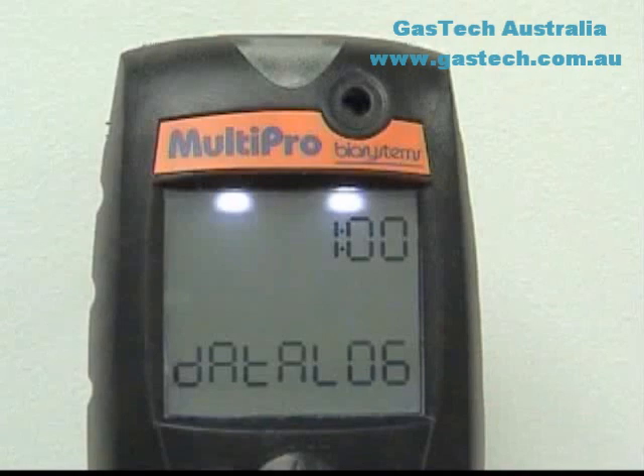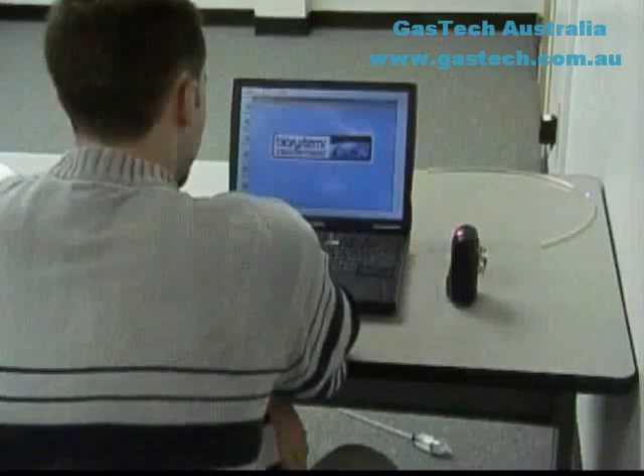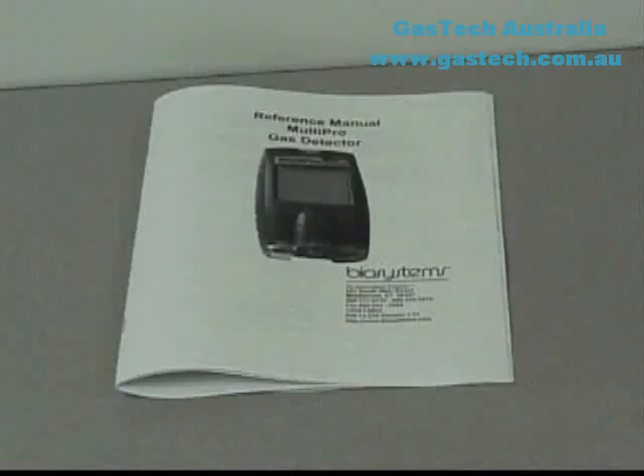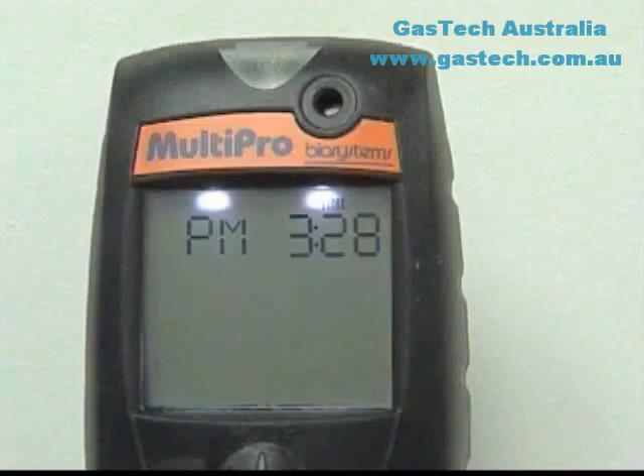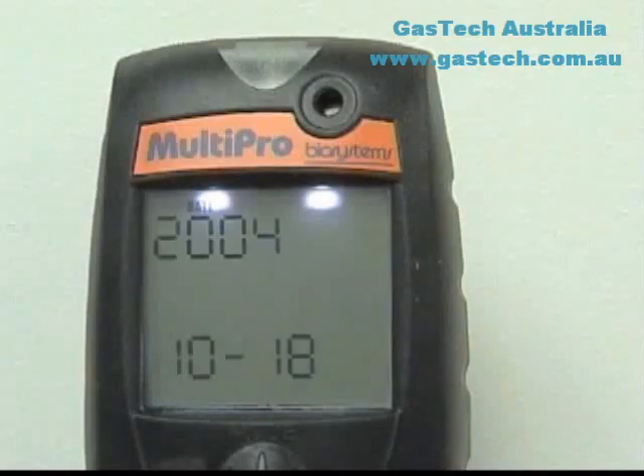The sampling interval can be modified with Biosystem's BioTrack program using a PC with an IRDA port, or the sampling interval can be modified directly with the mode button on the instrument. Direct programming options are covered in the Multipro reference manual. The time and date will then be shown.